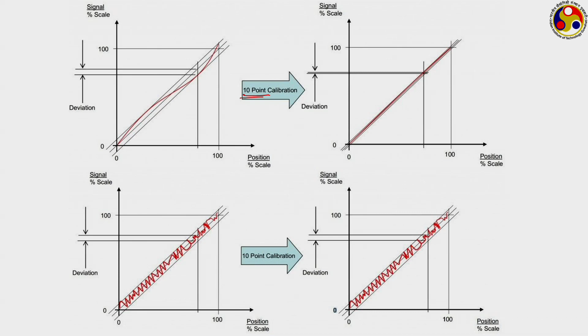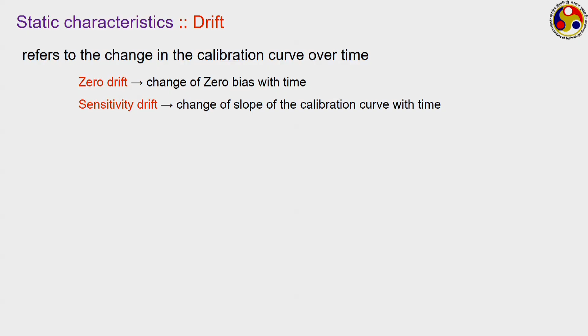Once you have calibrated the instrument, because of aging, wear and tear, or certain damage, the calibration may get shifted. We generally have two kinds of drift: zero drift and sensitivity drift. Zero drift refers to a change in zero bias, where the original curve develops a bias over time. Sensitivity drift is where the slope of the curve itself changes. In some cases, a combined curve shows both zero and sensitivity drifts present together.